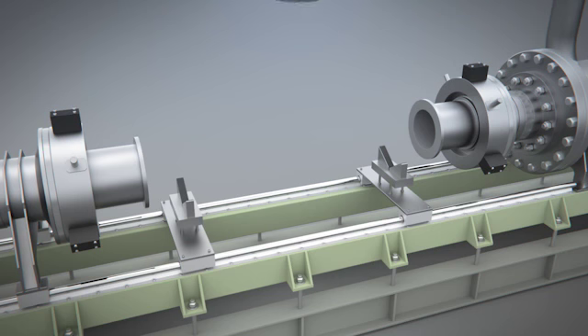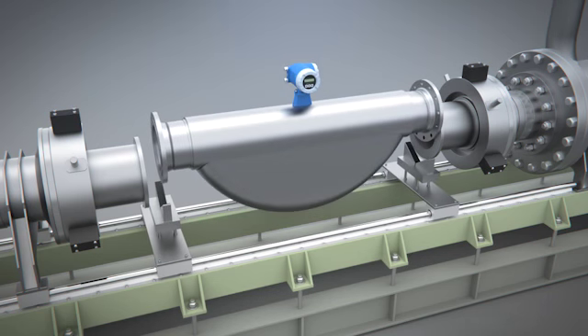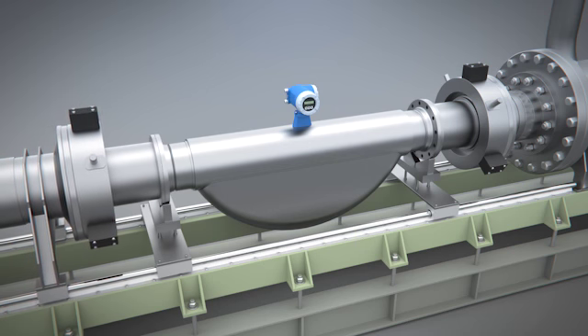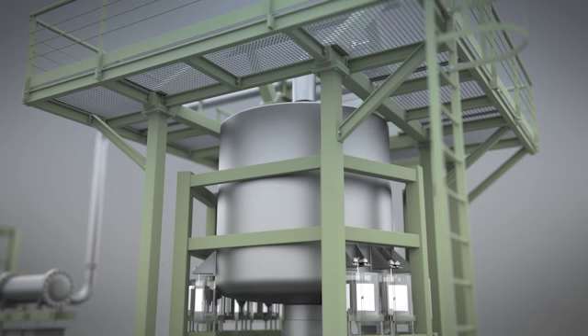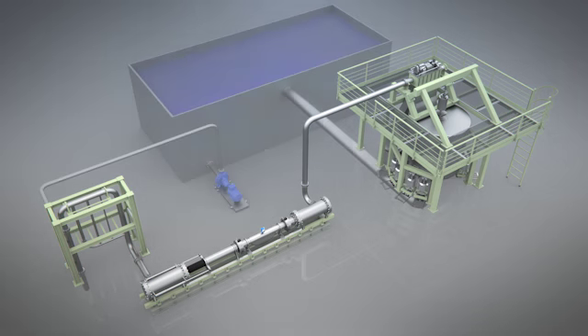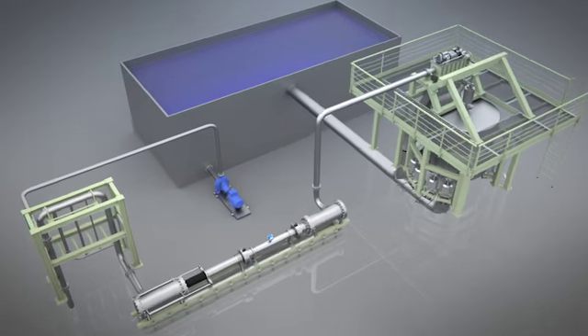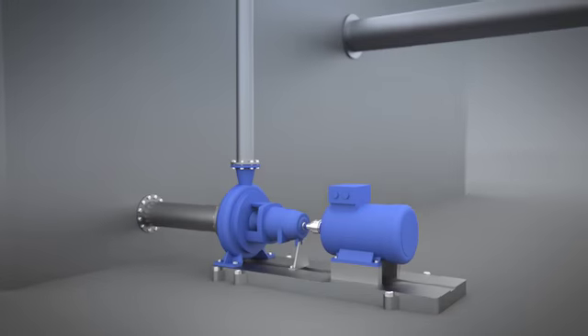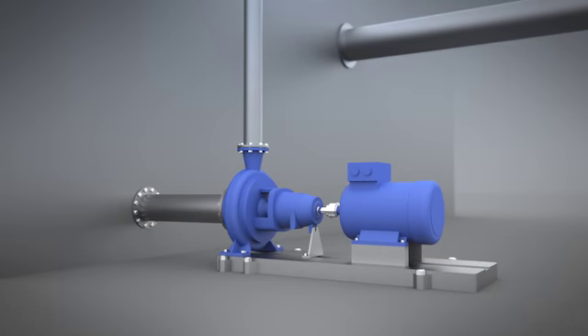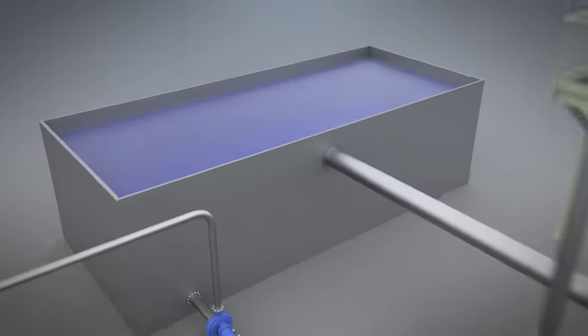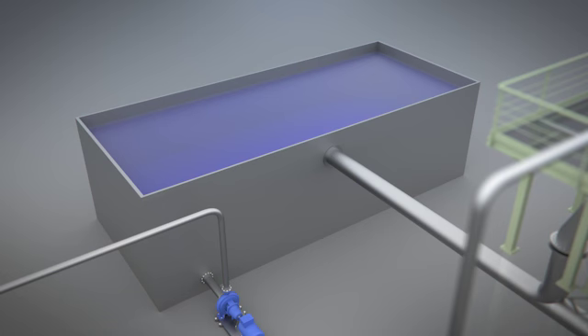During calibration, it is determined to which extent a value displayed on a flow meter deviates or not from a defined reference. To do so, the device under test is installed in the measurement section of the calibration rig and then connected electrically to the control system. The device and the reference itself, a high-precision calibration scale, are connected to each other by a system of piping that forms a circuit. A pump ensures a uniform flow of water through the pipeline, and a supply tank ensures that enough water is available for the calibration measurement.